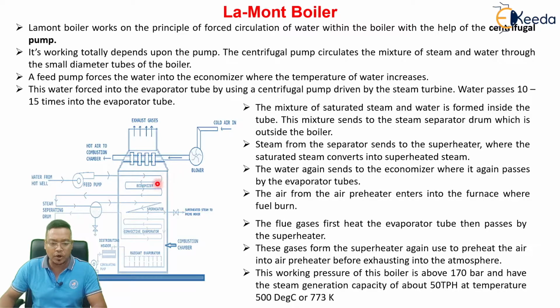Now the water has come into the economizer and through the economizer it is going into the steam drum, and in the steam drum water is taken from the downcomer and this water is pumped into the radiant evaporator with the help of the circulating pump, and this circulating pump is a centrifugal pump driven by steam. Now in the radiant evaporator, the water and steam mixture will go into the convective evaporator, and through the convective evaporator this water and steam mixture will go into the drum. In the drum, steam separates from the water and the steam will go into the superheater, and after superheating, the steam will be sent to the turbine for further expansion, and here water will again be taken through the downcomer and it is again going into the evaporator. This cycle repeats. Okay, this is the steam and water cycle.